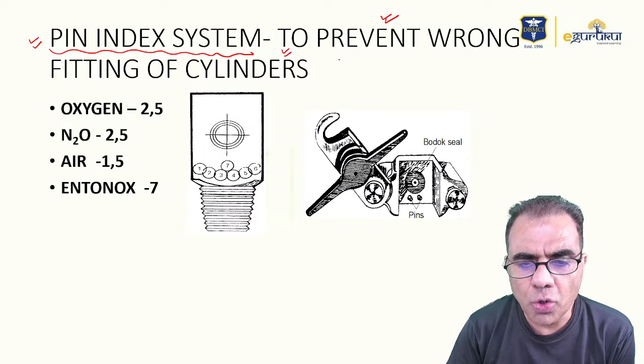Another very important thing you must know about cylinders, which is partially a part of the cylinder and partially a part of the anesthesia machine, is the pin index system. The pin index system is used to prevent wrong fitting of cylinders to the anesthesia machine. If you fit a nitrous oxide cylinder in place of oxygen, the patient receives 100% nitrous oxide and is definitely going to die. So there should be a system which prevents wrong fitting of cylinders, and that is the pin index system.